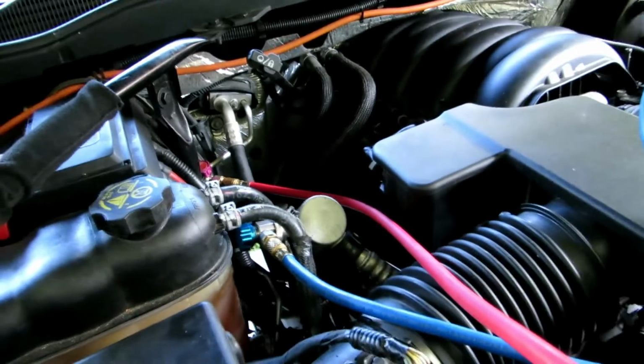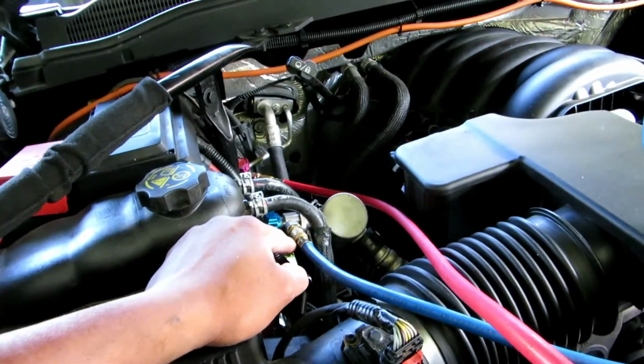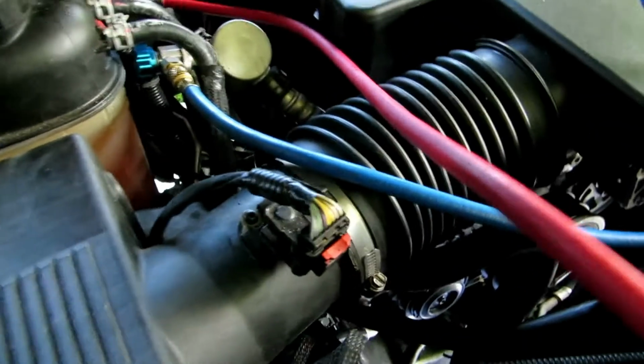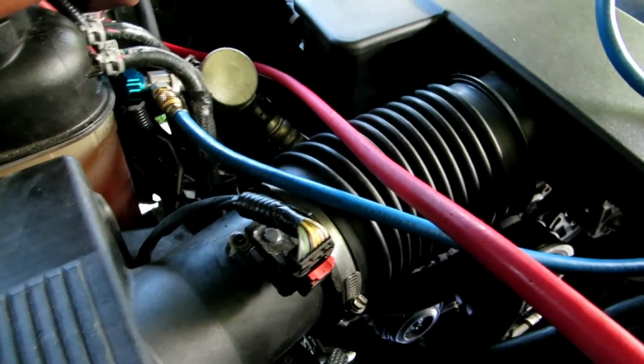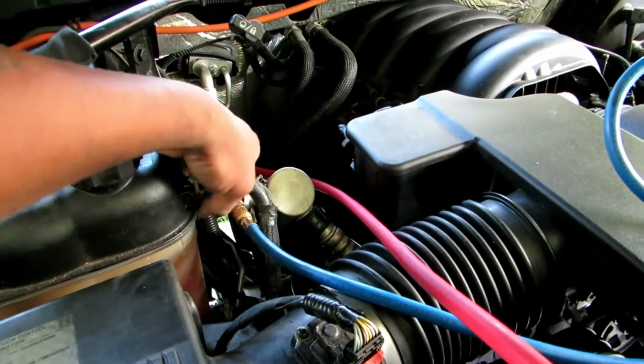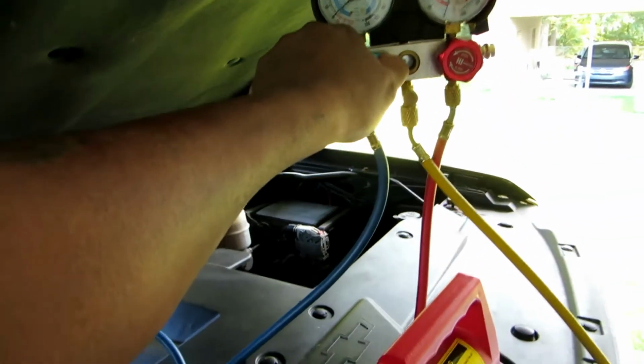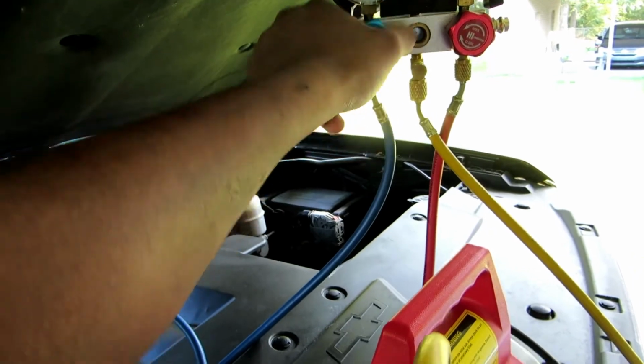As you can see here, I got the expansion valve put in. That's the easiest thing I did to this thing. I put a new Schrader valve in right here the last go around, because it was leaking. So go ahead and get this vacuum started. Open everything up. Make sure all the valves are open. Then we open this, and you'll hear the sound. You hear it?